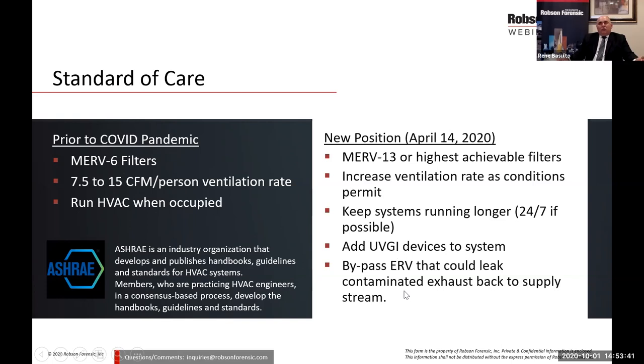One other item I found interesting in the position paper is they're saying go ahead and bypass all ERVs. ERVs are energy recovery ventilators, because some of these could leak contaminants from the exhaust back to the supply. What ERVs do is take the air that you're exhausting from your building and, in a heat exchanger, use it to pre-treat the air that's coming in. Some ERVs have a cross-contamination component in there. I know this; it depends on which one you use. In the dog intake facility we just did for the animal shelter, we put one in, but we made sure that the heat exchanger doesn't allow for that cross-contamination. So there are different types. I just found it interesting that they had that in there.